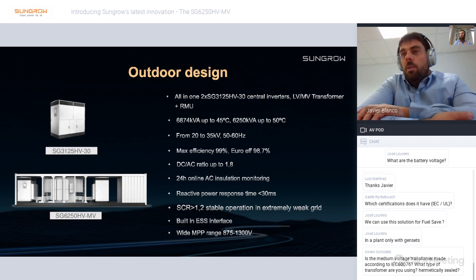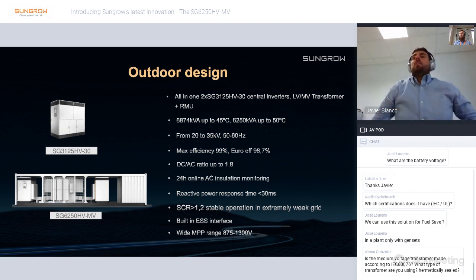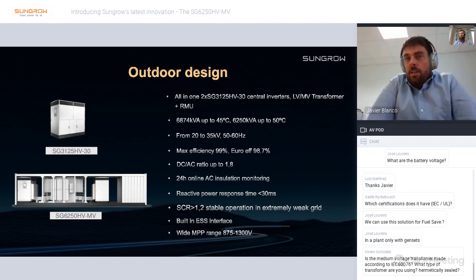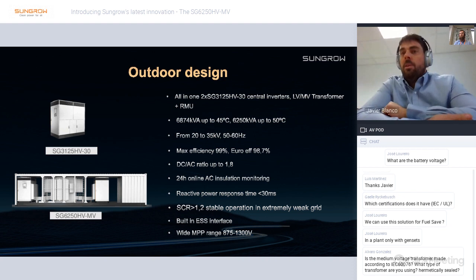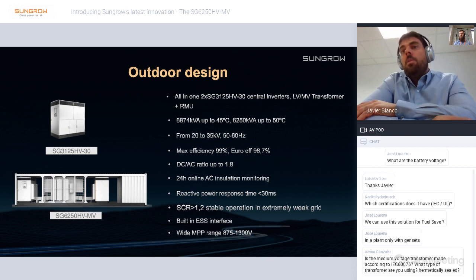Medium voltage transformer according to IEC 60076. Good question. It is not only in compliance with IEC 60076, but also with eco design for use in Europe, meaning very reduced losses in the LV-MV transformer. We are even considering, for the next stage, the application of the European standard for eco design of transformers starting on July 2021. Be aware that we are having that in mind for deliveries after July 2021.